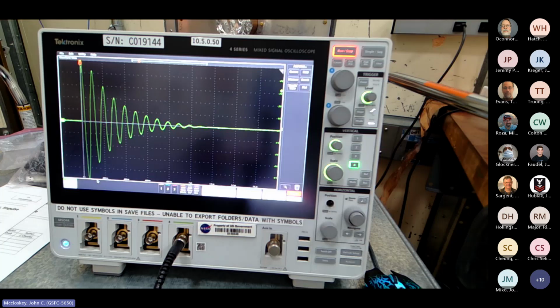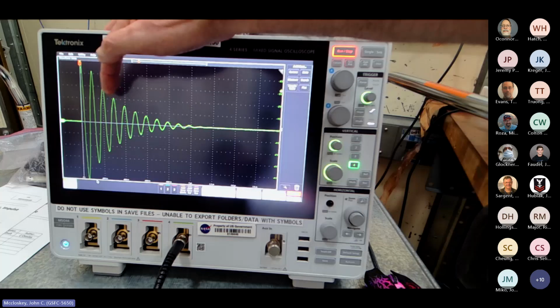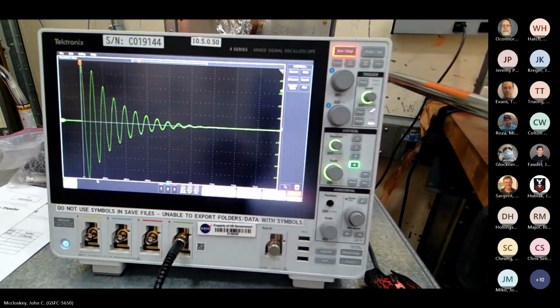Okay. And then remember that you want the 50% peak to be around the 4th or 5th peak for full compliance. And so the 3rd peak is around 60%. That's 3 volts out of 5. And then the 4th peak is about 40%. So we don't have a peak that's right at 50%, but effectively it would be between the 3rd and the 4th peak. So that's okay. Remember that the 3rd peak was just barely out of the specified range, like 9, where the range is 10 to 20 for that Q factor. So again, there's not a whole lot you can do about it.